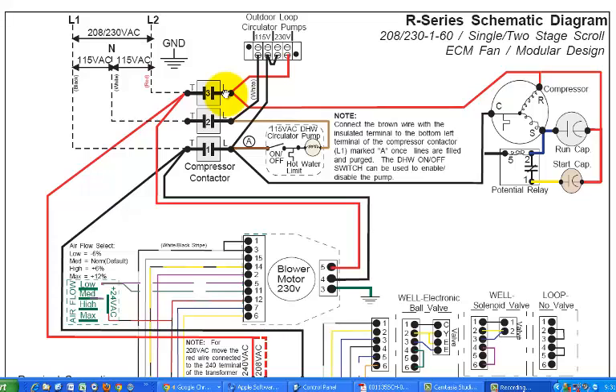And what's happening within this compressor contactor or relay is that there's going to be a magnetic coil, and when that magnetic coil is energized, it pulls the contact terminals into place with each other. And as I said, we're going to look at how that magnetism part of it happens in a separate video. But for now, all we have to think about is the fact that when this thing is actuated, we're going to have continuity between the left-hand side and the right-hand side on each one of those terminal points. So ultimately then, when the compressor contactor is actuated, we're going to have 240 volts showing up between this lower terminal on the right-hand side and the upper terminal on the right-hand side.